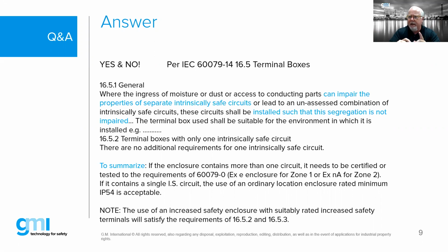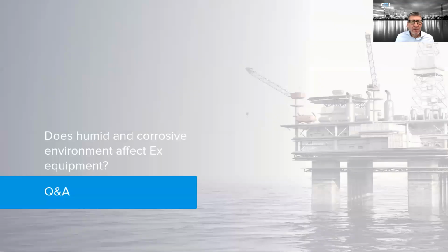Now, if we take a dual channel barrier and we have two circuits coming into a junction box, and then from that junction box we branch off one way to one device and then to another device, at that point that box would actually have to be certified. Okay, that's very clear. So, question, does humid and corrosive environment affect EX equipment?